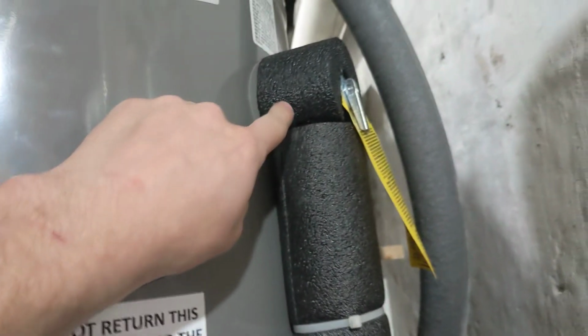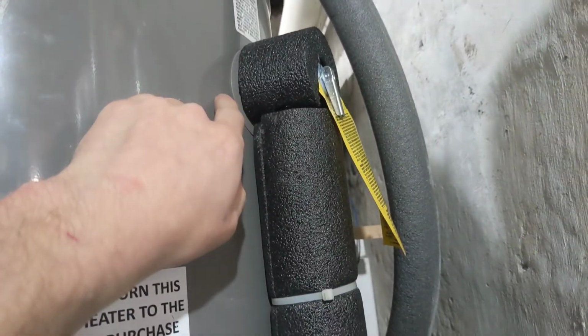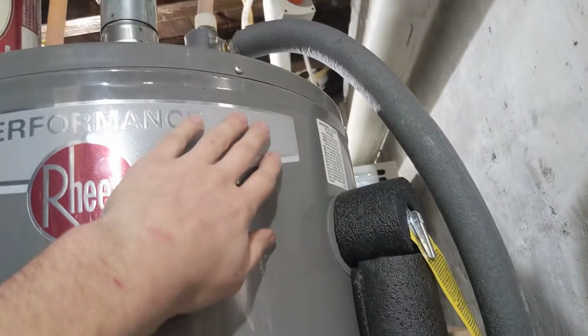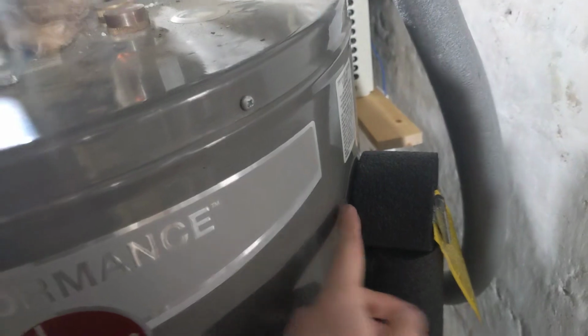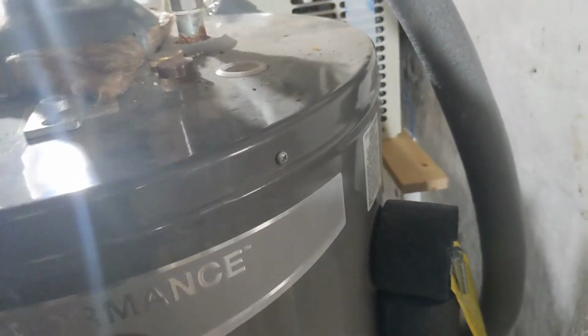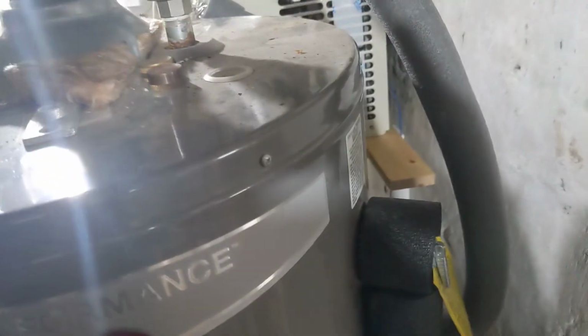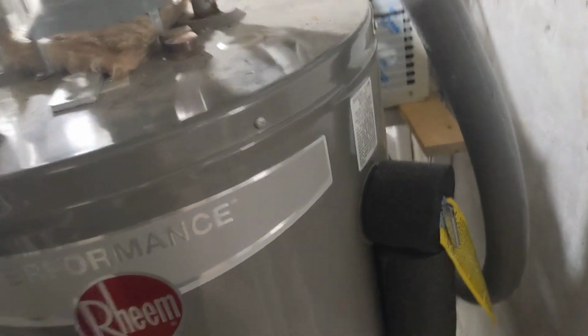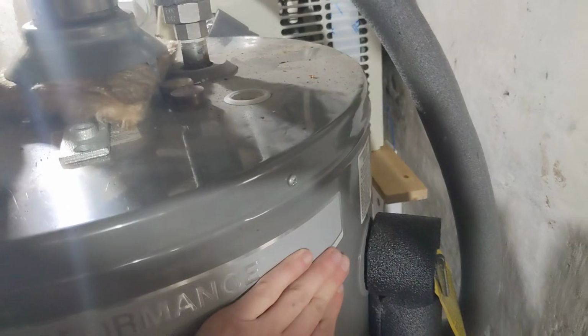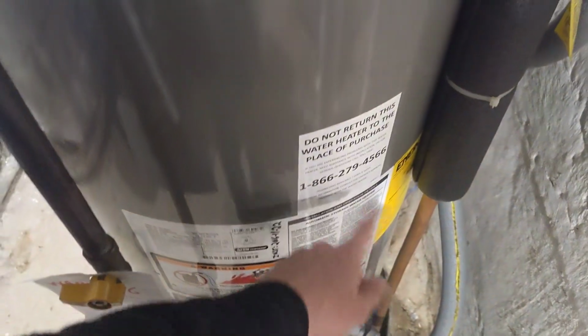Now this setup was originally configured where I was putting the heated water back in through the pressure relief valve port. And that was a problem because the pump was taking the water out of the bottom of the tank, heating it slightly, putting it into the pressure relief valve port, which is at the top of the tank. What you were doing then is you were taking water that was cold at the bottom of the tank. You might have been adding 5 degrees to it, and then putting that water into the top of the tank, which has hot water in it. And it was diluting the temperature of the hot water that was already in the tank, and the shower would start to cool down noticeably during a shower because we were taking that nice 135 degree water that was up here and we're blending it with cold, slightly heated water from the bottom of the tank. It was effectively destroying the temperature in the top of the tank.